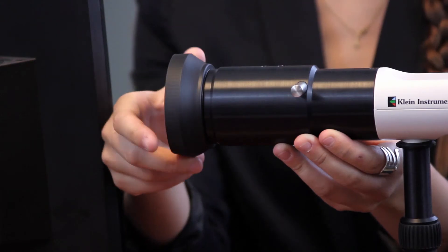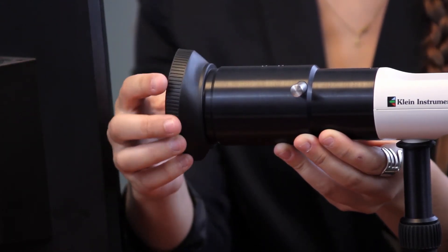Now we can actually position our colorimeter. The K10A was designed with the ability to measure displays from far away, but for now we will place it close to the screen to eliminate ambient light. The lens hood may also assist in eliminating light.